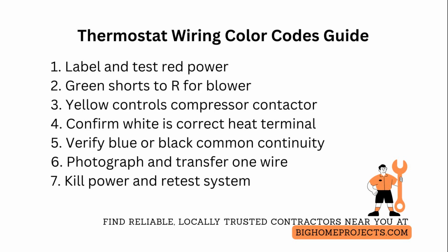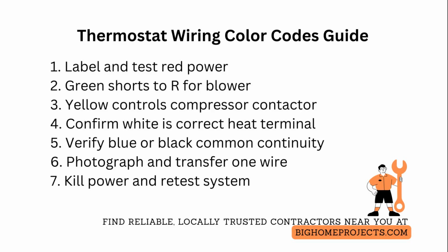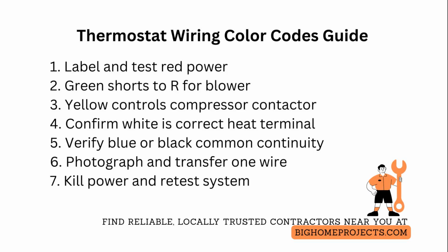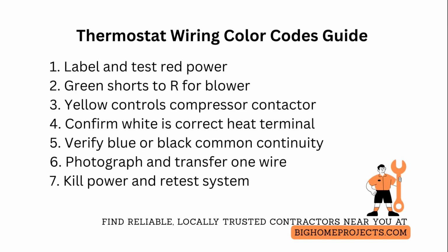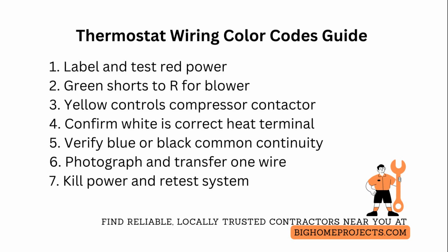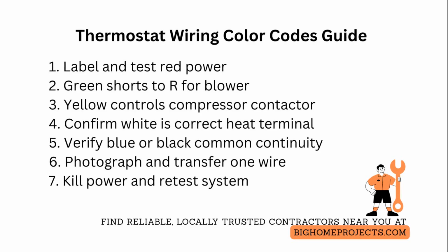If you have a heat pump, there will be additional functions like changeover valve control labeled O or B and reversing valve wiring that must be handled differently. When replacing a thermostat, photograph the existing terminal strip, write down every wire, color, and terminal letter, and transfer one wire at a time to the new stat to prevent cross-connection.